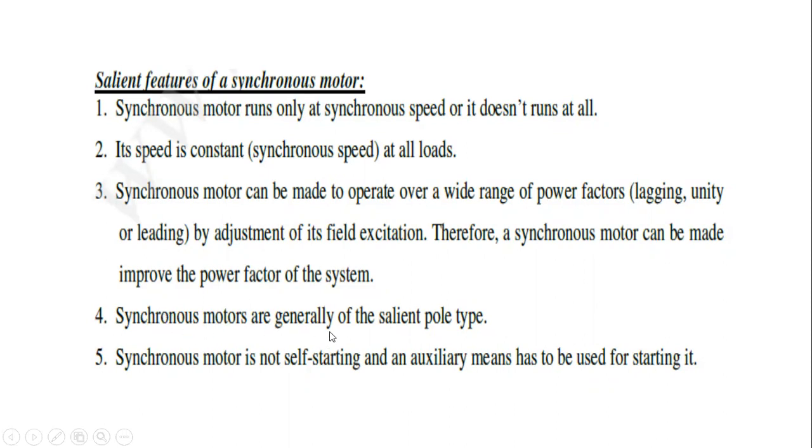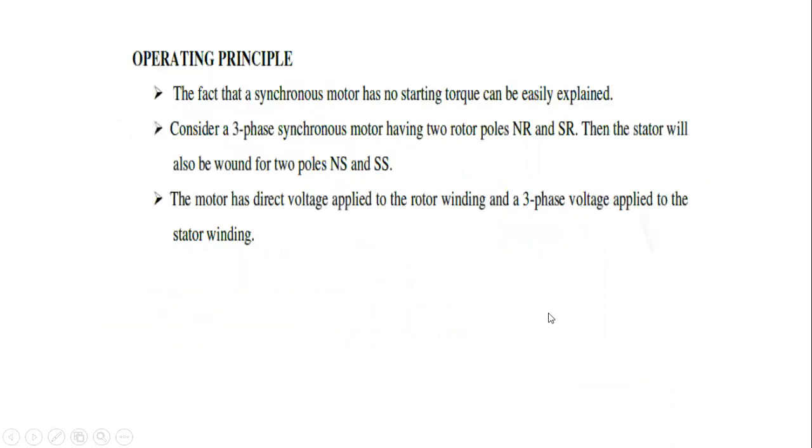The synchronous motors are generally of salient pole type. The synchronous motor is not self-starting, and auxiliary means have to be used to start it. Next, what is the operating principle? The synchronous motor has no starting torque. That's why we use another equipment for starting the motor, because it is not a self-starting motor.